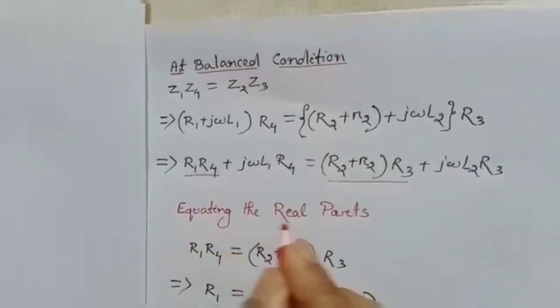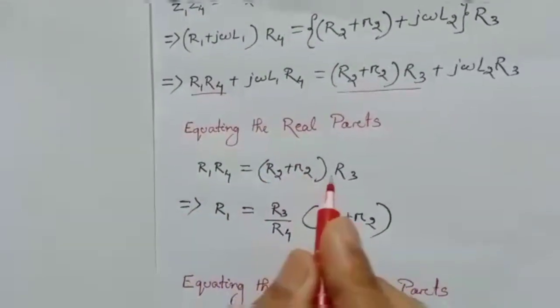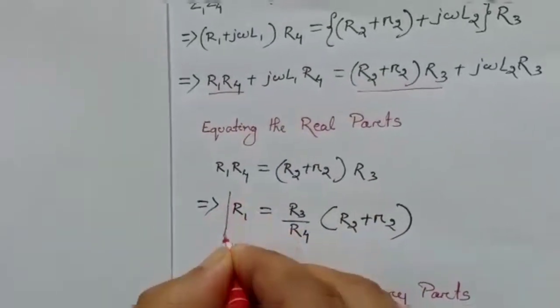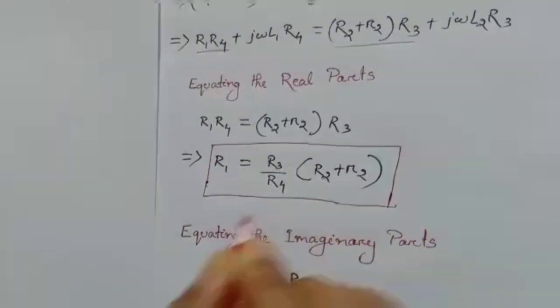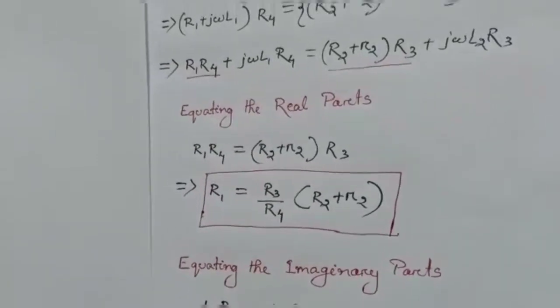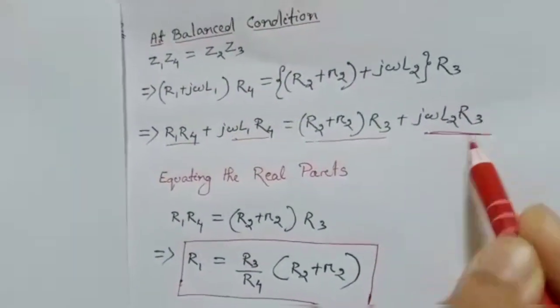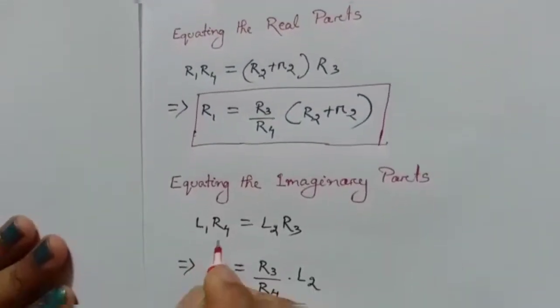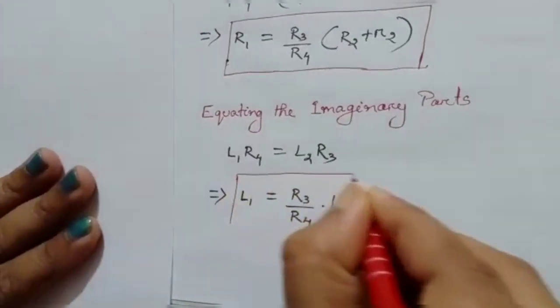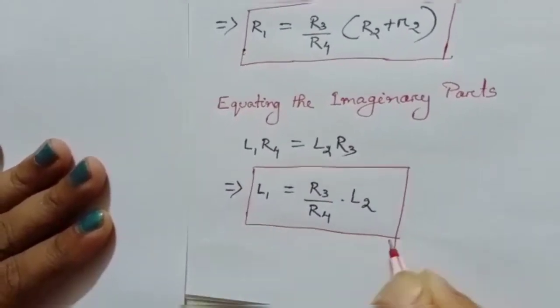After equating the real parts, we get R1 × R4 = (R2 + r2) × R3, from which the unknown resistance R1 = (R3 / R4) × (R2 + r2). Similarly, equating the imaginary parts gives L1 × R4 = L2 × R3, and finally the unknown inductance L1 = (R3 / R4) × L2. So L1 and R1 are the two unknown quantities found using the balanced bridge condition.